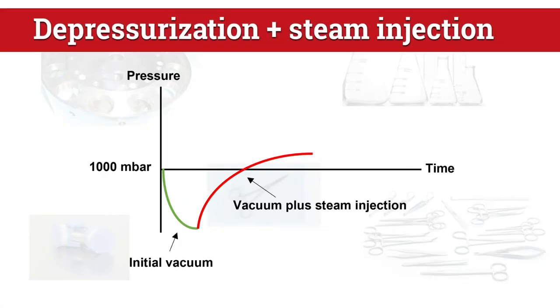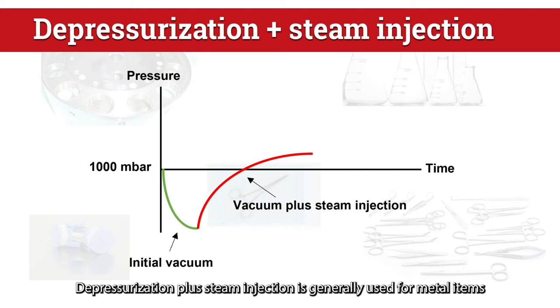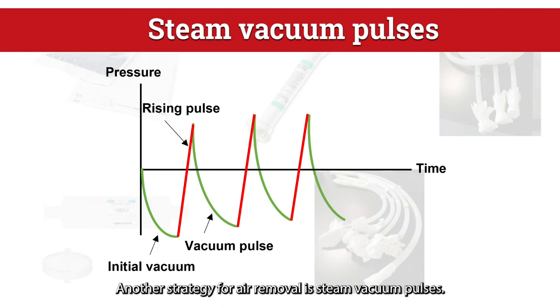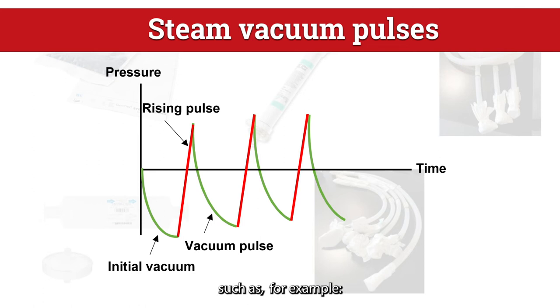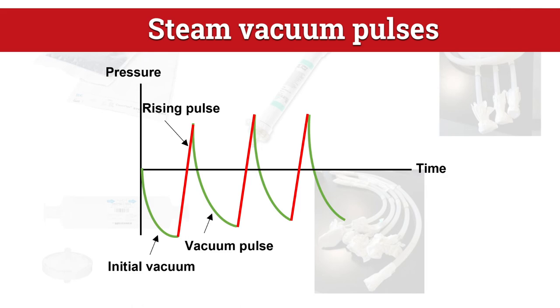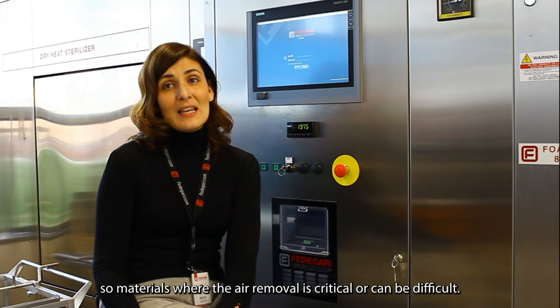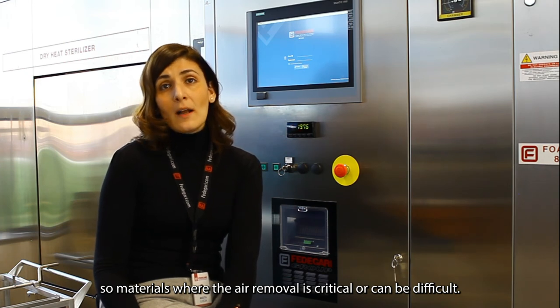Depressurization plus steam injection is generally used for metal items and open glassware. Another strategy for air removal is steam vacuum pulses, which is generally used for porous hard materials such as stoppers in bags, filters, and similar materials — items where air removal is critical or can be difficult.